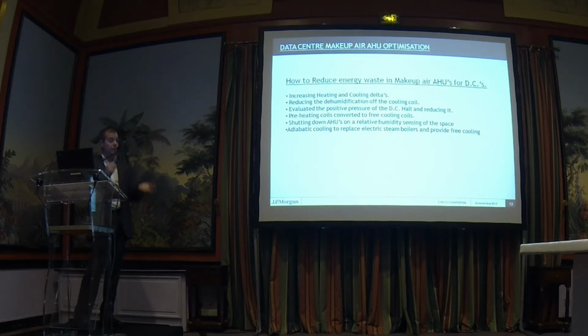So the temperature where you want to heat the air and the temperature where you want to cool the air, the wider that gap, the better. Reducing the dehumidification of cooling coils: if you've got a wet coil running at 6 degree chilled water, you're going to have to humidify because you're stripping the moisture off it. Trying to blow air into a data center that's running hot, naturally you always want to push the humidity out of the space.